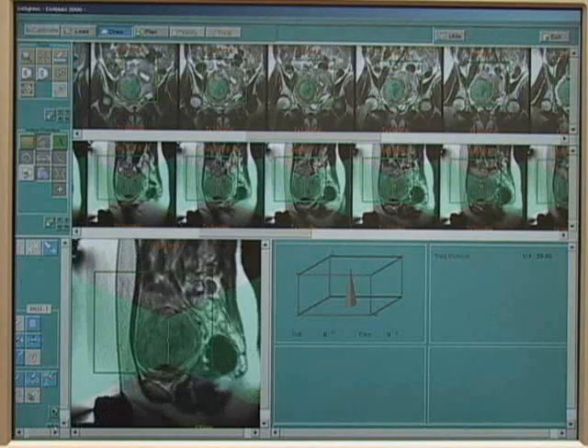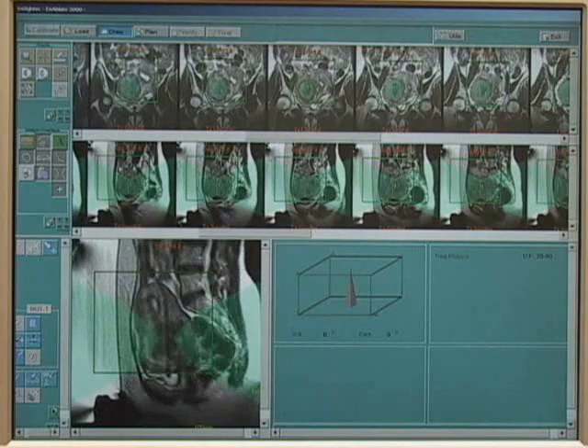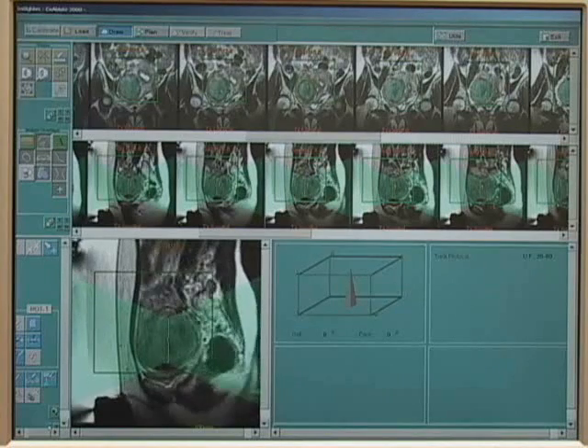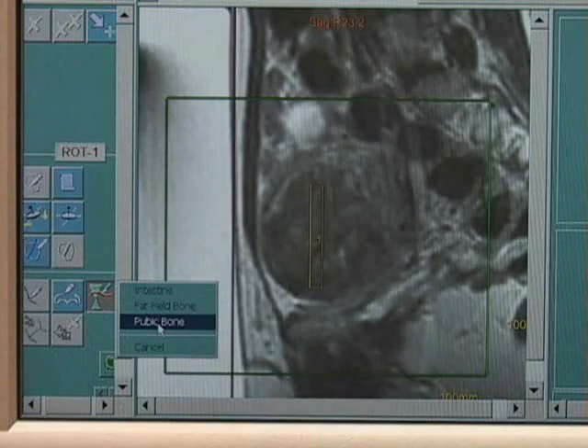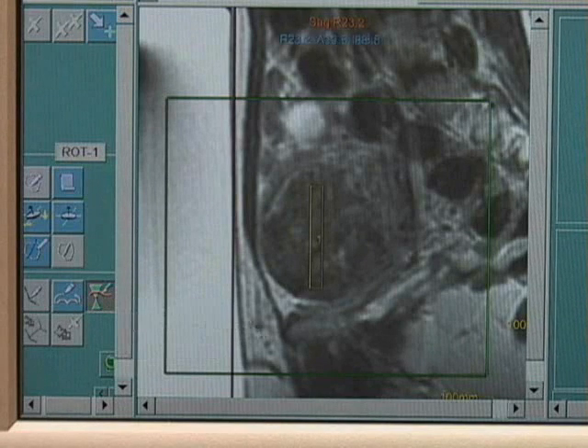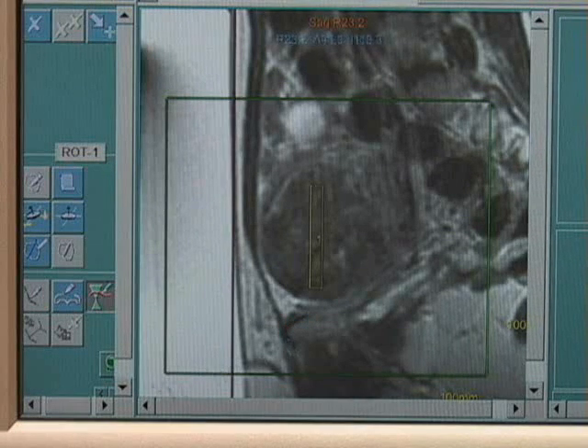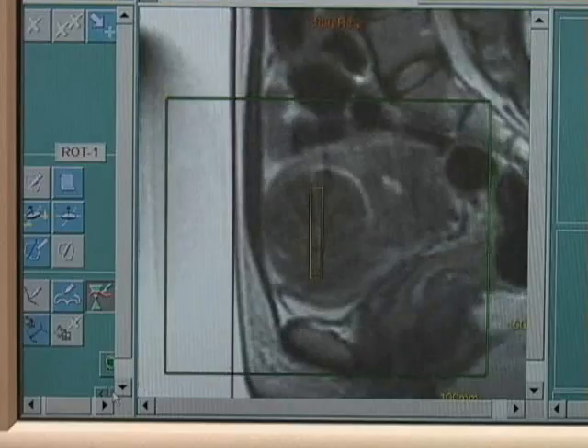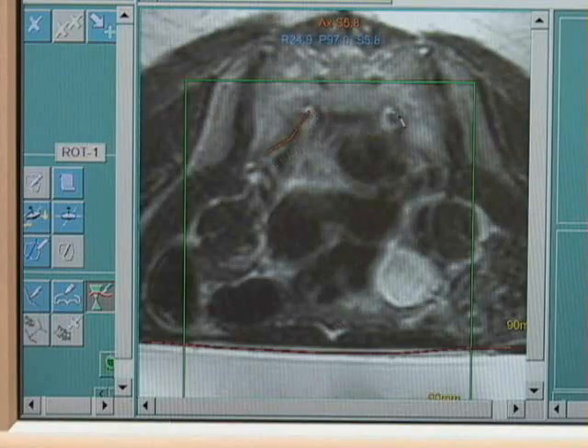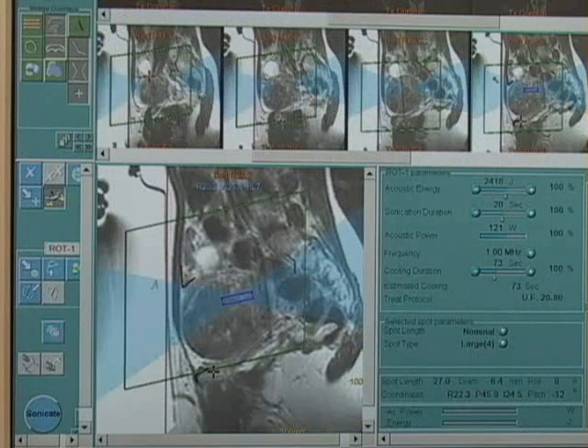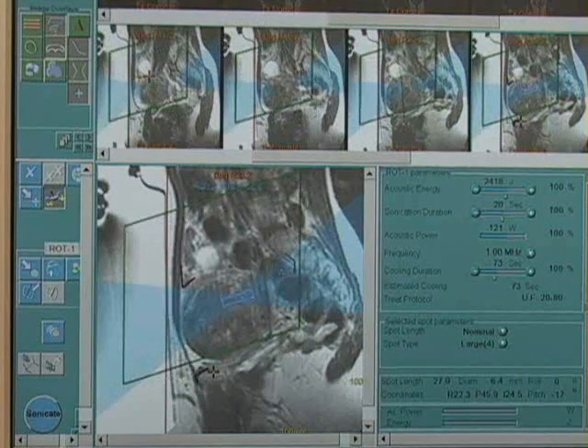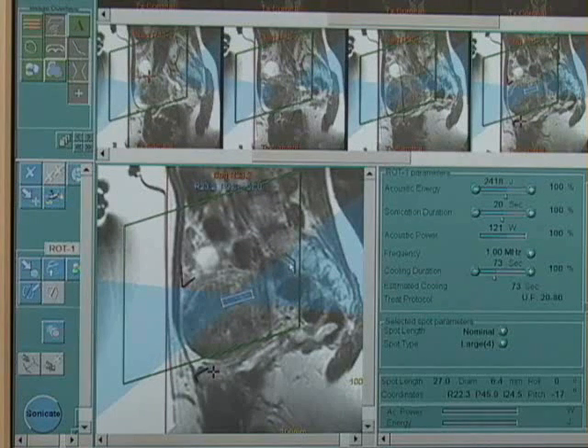As a safety measure, to prevent the energy beam from passing through sensitive organs such as pubic bone or bowel, and to limit the energy density at specific areas, like skin or bone surfaces in the far field, contours are drawn around these organs. After drawing the contours, the system automatically checks the beam path of each sonication point. The system issues a warning if the energy density exceeds set safety limits.